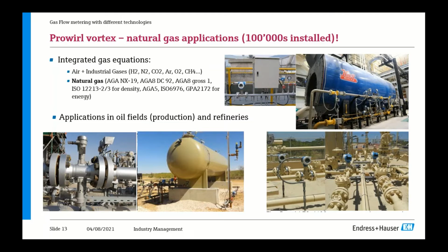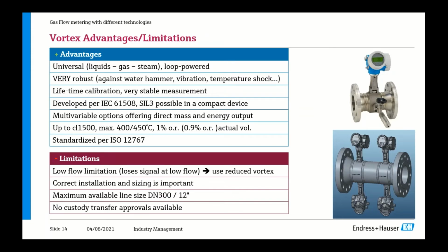And with the integration of pressure and temperature, you also get the gas equations like AGA8, DC92, or the Gross method, or the energy calculations like AGA5 or ISO 6976. On the next slide, you see an overview of the benefits or advantages of using a vortex meter. Our meters are universal. You can use them in liquids, gas, and steam. That's why very often in refineries you find them being used.